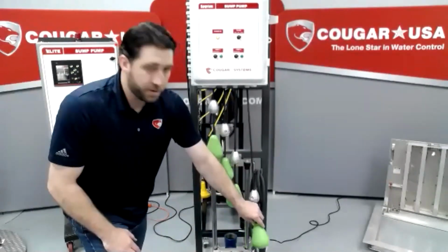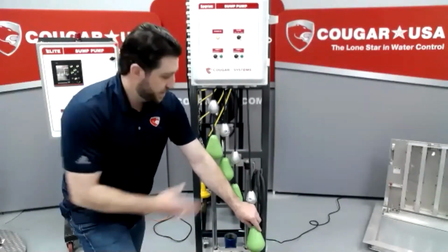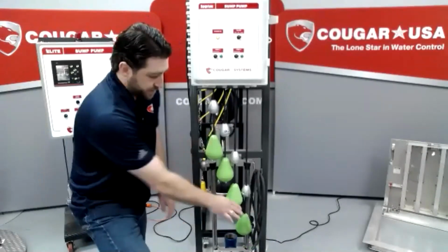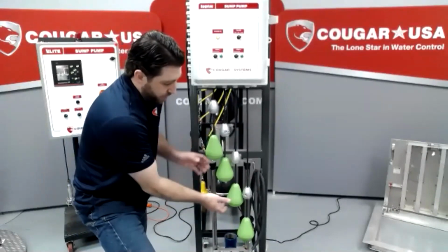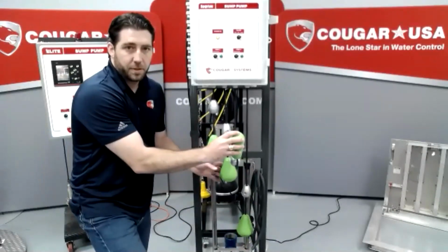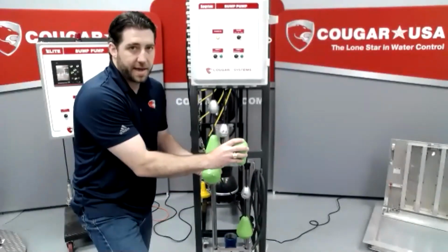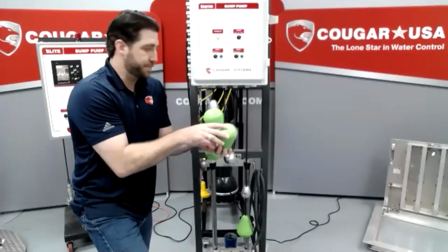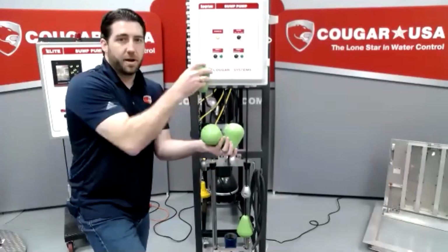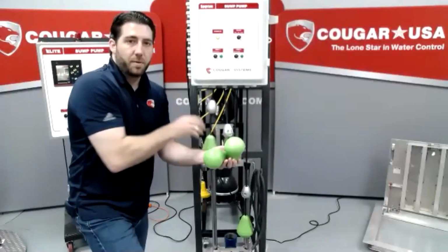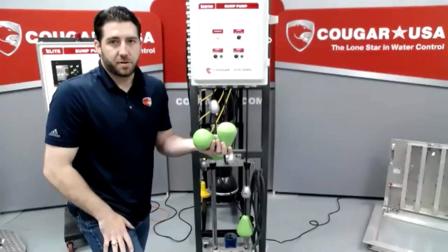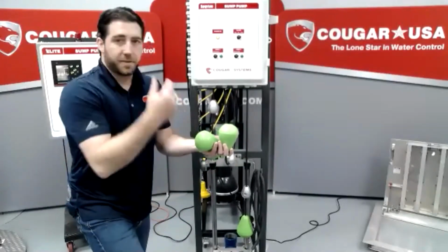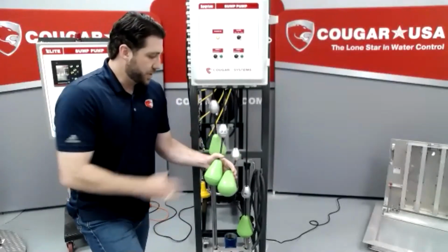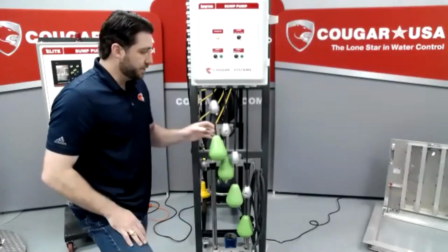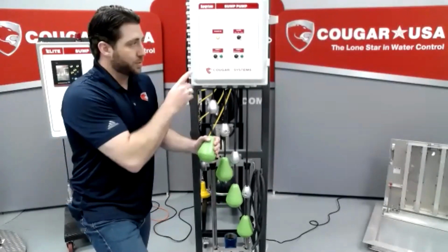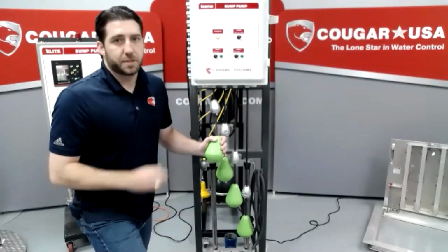The other thing that's important about this float switch is it has to come up for the other ones to work. So if this gets hung up down or it's bad, it's not working, and our pump goes to turn on, the lead pump on, nothing's going to happen. Lag pump on, nothing's going to happen until we get to our high level. We get a high level, but with most of these styles, they're not going to actually turn on the pumps. They just give you high level. So nothing's going to bring on these pumps. So we designed this to where this high level float is going to bring in both motors and run both pumps.